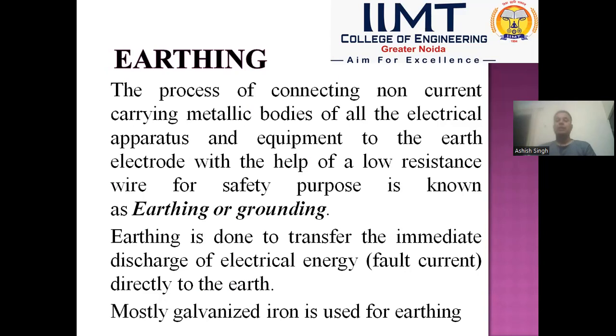After discussing MCCB, we further move to our next topic, that is earthing. It is a very important topic in electrical installation. Before starting earthing, we have to know what is earthing, why it is done, and how it is done. Why are we using earthing? What is the need of earthing? So earthing is mainly the connection of non-current carrying metallic parts of appliances to the earth with the help of a low resistance conductor. So earthing is the process of connecting non-current carrying metallic bodies of all electrical apparatus and equipment to the earth electrode with the help of low resistance wire for safety purposes.